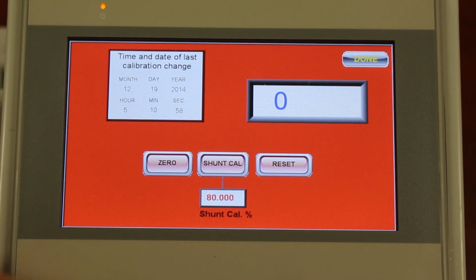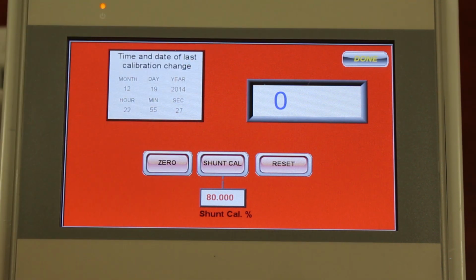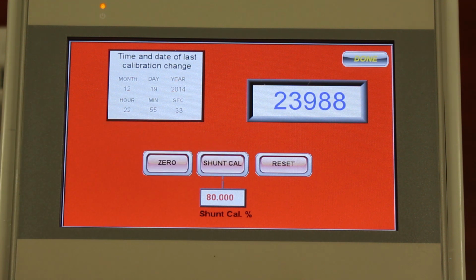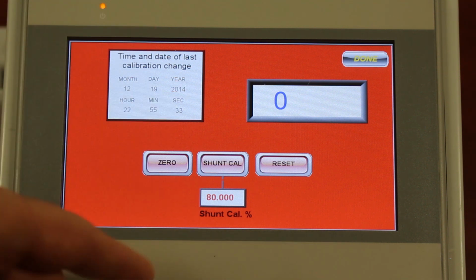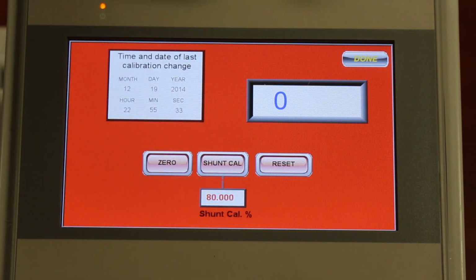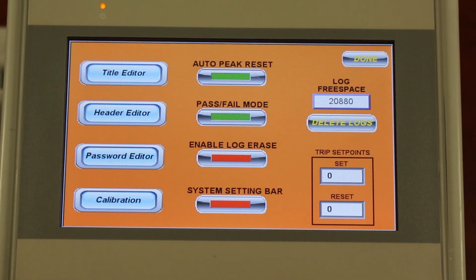When you calibrate the unit, you simply hit the 0. It'll zero it out if it's not already zeroed. And there's a shunt cal button, which simulates pressure to 80% of the range of the transducer. Today we're working with a 30,000 psi transducer, so it'll run it up to 80% of that and do the shunt cal on it. And once you do that, you're done with the calibration.